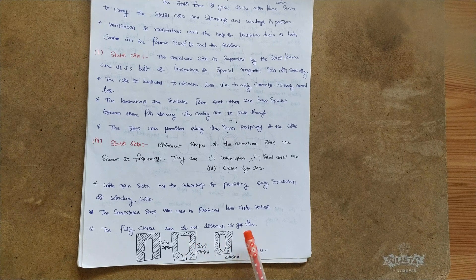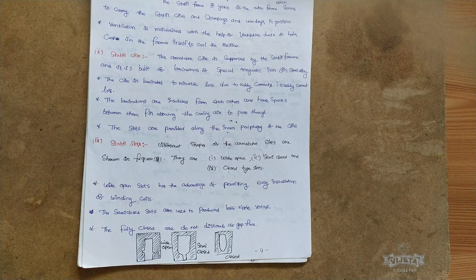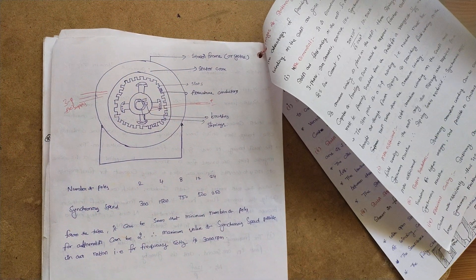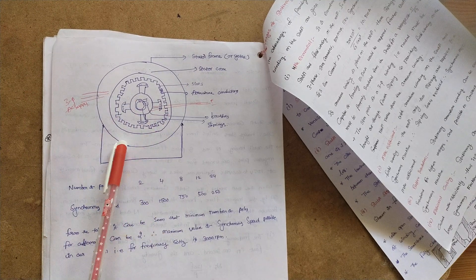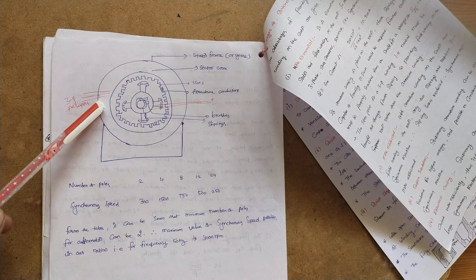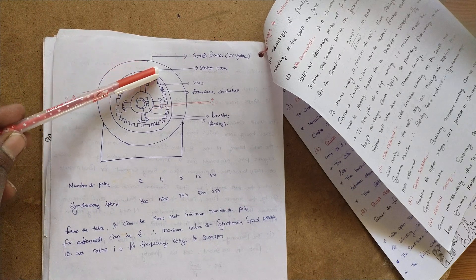Fully closed slots do not disturb the air gap flux, producing more uniform sinusoidal voltage with fewer ripples. The construction of the synchronous generator stator shows slots where armature windings are placed - semi-closed or closed type are preferred. Three-phase supply connects to the stator. The main parts are: stator frame or yoke, stator core, armature windings, and slots.